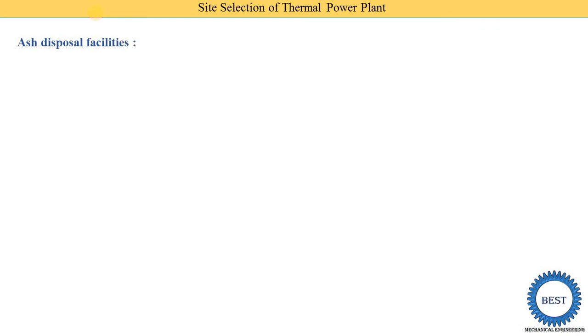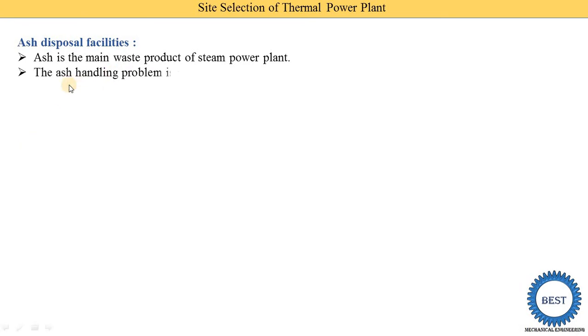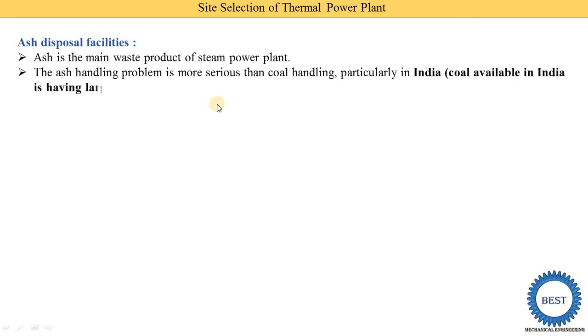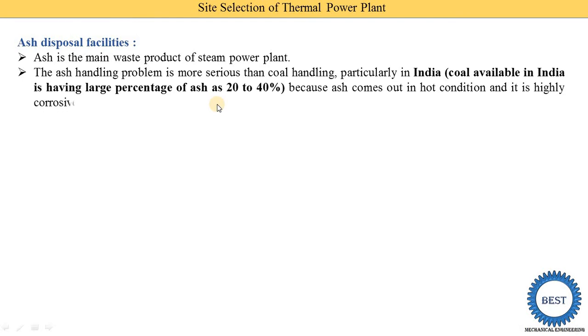Next point is ash disposal facilities. Ash is the main waste product of a steam power plant. The ash handling problem is more serious than coal handling. In India, coal has a large percentage of ash — 20 to 40 percent — meaning if we burn 100 kg of coal, 20 to 40 kg of ash is produced. Ash comes out in a hot condition and it is highly corrosive, making ash handling more difficult than coal handling, which is at normal atmospheric temperature.